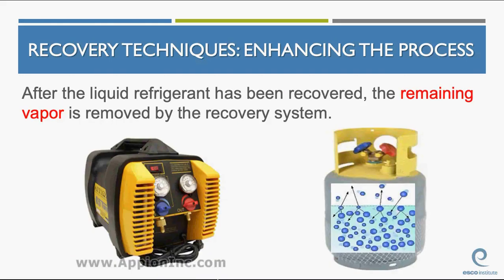After the liquid has been recovered, the remaining vapor is removed by the recovery system. Your recovery system, especially the newer recovery units, is always going to want to remove the liquid first and then the vapor. Okay?